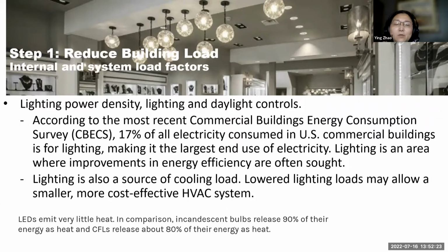For example, use LED lighting. The LED emits very little heat compared to other types of lighting fixtures. Incandescent bulbs release 90% of their heat into the building space. And the CFL, compact fluorescent, releases about 80% of its energy as heat.